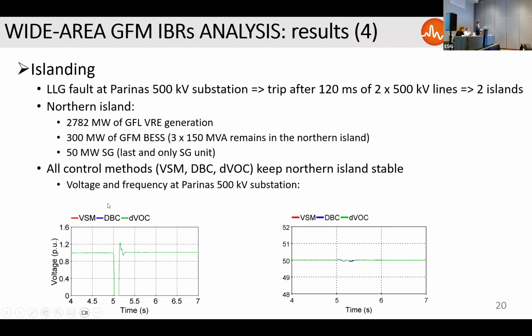So as you remember, in the north, you have PV, and basically that's it. However, with the grid-forming converters, they were able to stabilize this island without any problem, and the frequency got back to normal, the voltage got back to normal with any of the control modes that were discussed.